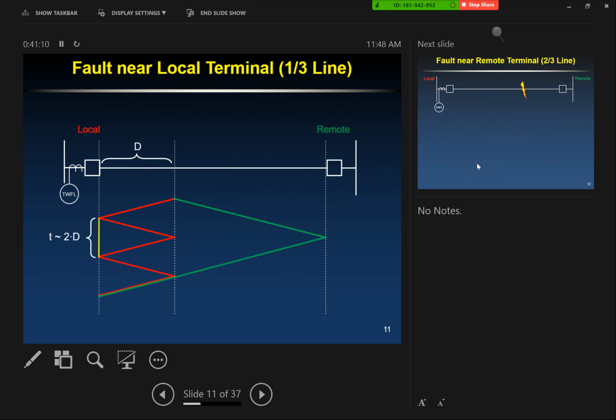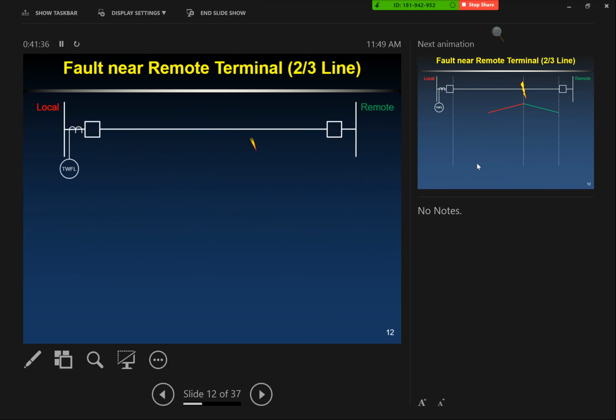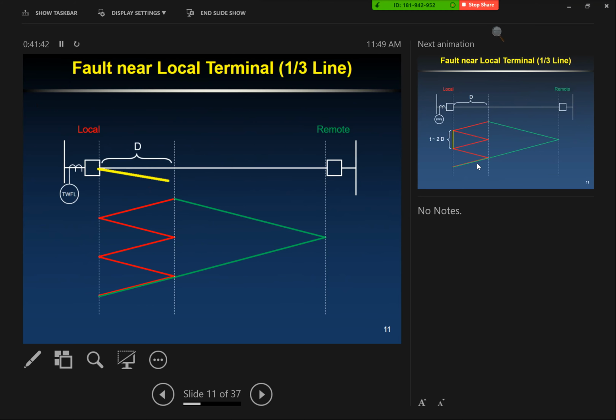So this would be your first traveling wave to arrive, and this would be the second traveling wave to arrive. This is a round trip travel, so we know that the time here is proportional to twice the distance since it's round trip. So when you pull up, if the world were perfect, a single-ended traveling wave event, you can see, here's my first waveform to arrive, second waveform to arrive, calculate the fault, the distance to the fault, no problem. We'll see it's not all that simple and friendly, but that's the theory there.